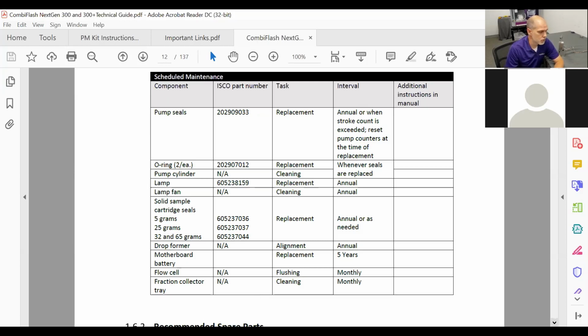All right, the drop former. Drop former is a part on the diverter valve, and the diverter valve is in the fraction collector arm. So when we do a separation on these devices, if you want to collect that separation, you have test tubes in the fraction collector area. And the arm is just that thing that we took the screw off earlier. So there's a drop former, and this is a shaped part that makes it so that you get droplets into the test tubes. It's not spraying everywhere or anything like that. This drop former can clog. It can become broken. Many different things can happen to it. So it's a good idea to check it. We want to do an alignment on it. That's done in the service menu. And we would recommend that you do that every year, just so you're not going to lose any sample off to the side of the unit it's collecting into test tubes.